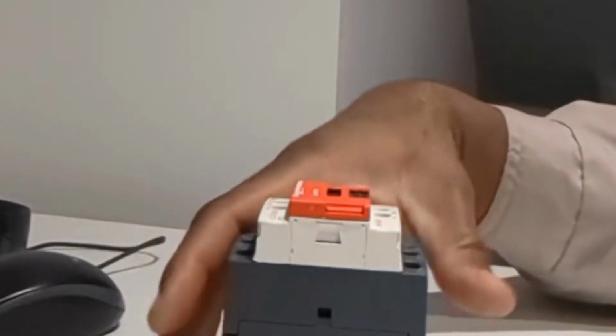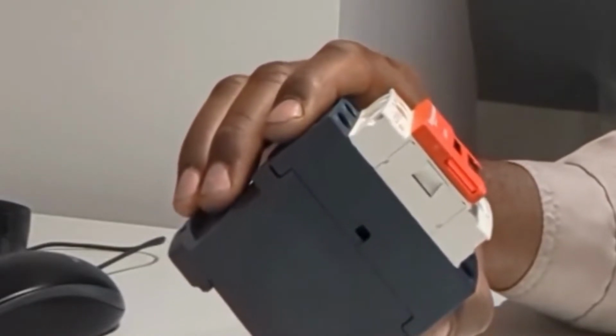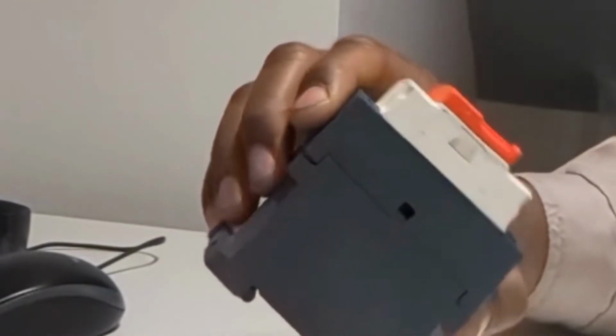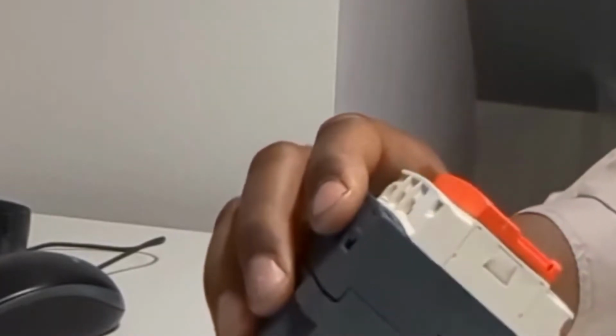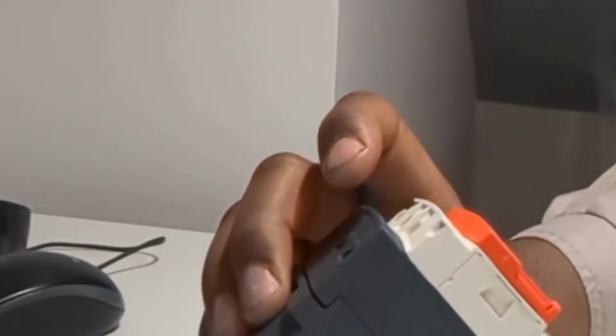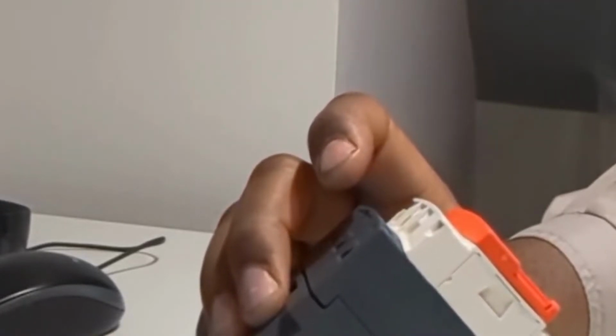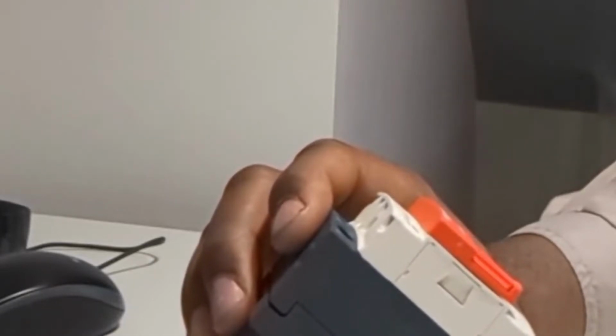On the face of a contactor, usually we have the normally open and the normally closed. We have the coil, and as well we have the contacts that allow the inflow of electric current. Usually L1, L2, and L3 are the terminals for the three electrical phases. So the three-phase cable passes through it and comes out from T1, T2, and T3. It only passes electricity to T1, T2, and T3 when the coil is energized.